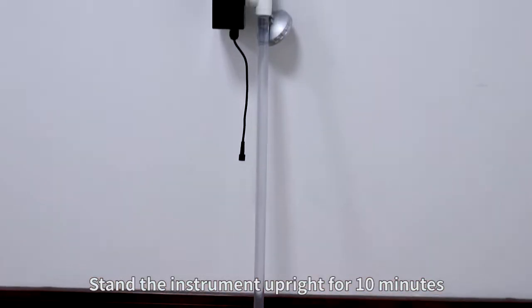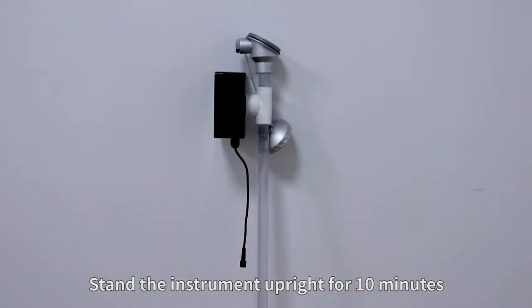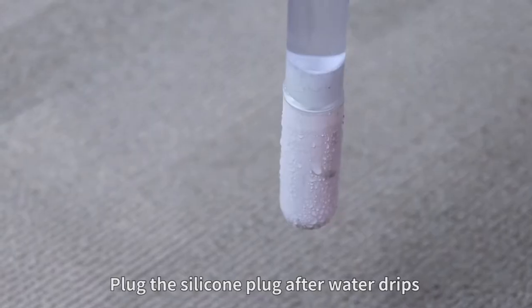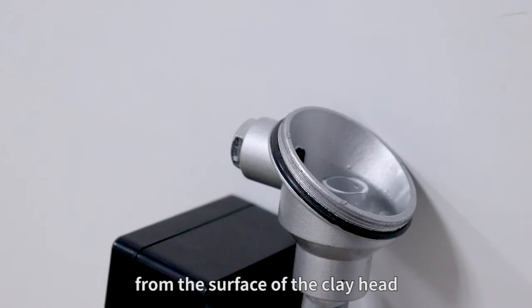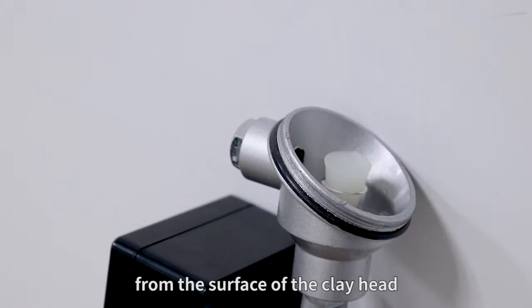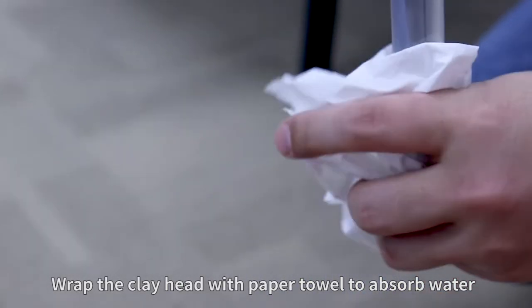Stand the instrument upright for 10 minutes. Plug the silicone plug after water drips from the surface of the clay head. Wrap the clay head with paper towel to absorb water.